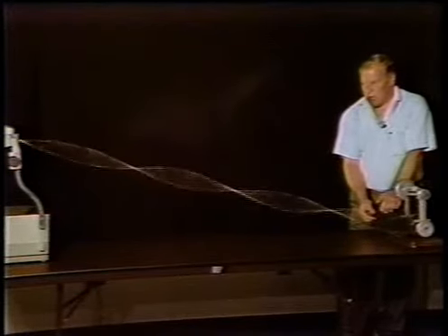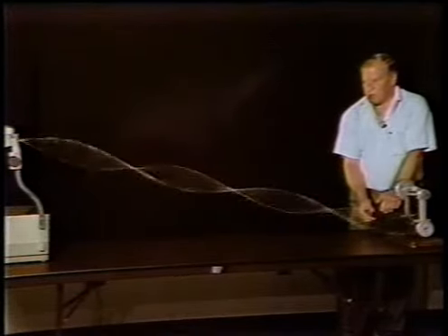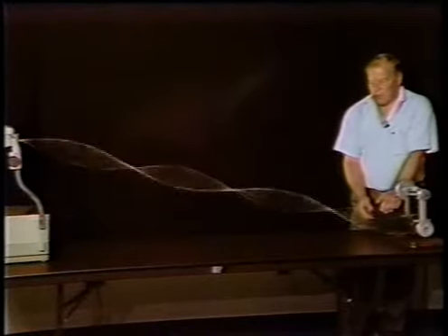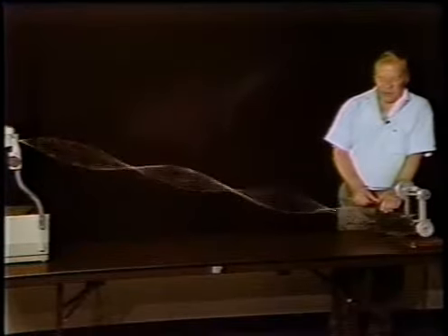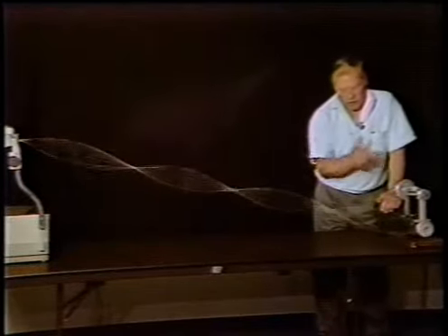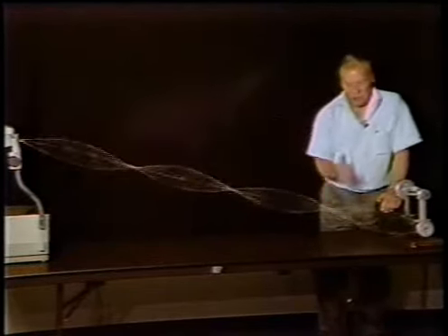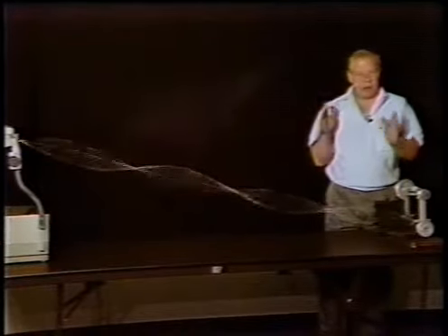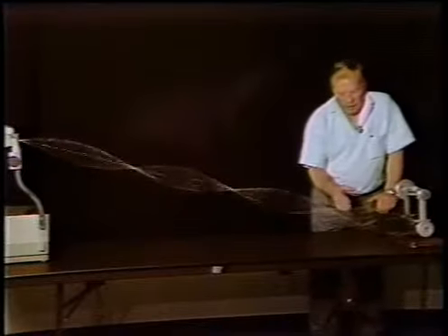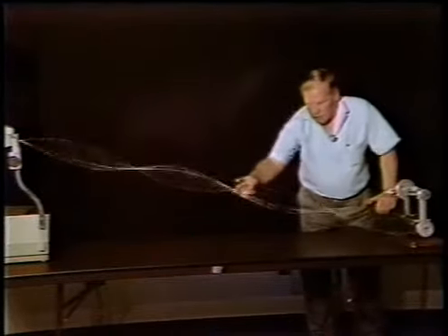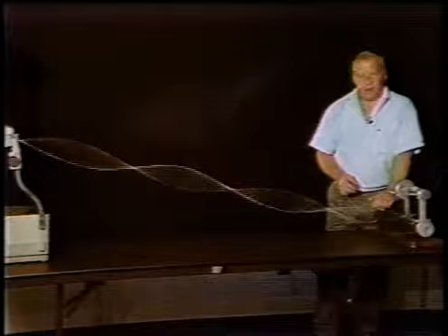Now we've reached an exciting force frequency. We are exciting now the fourth bending mode of resonance. And let's assume that this was a section of piping, perhaps. It's very, very common when you install your piping support hangers that you would install those at uniformly spaced distances. And this is something that you may want to avoid. You can see that these distances between nodal points are in fact uniform.